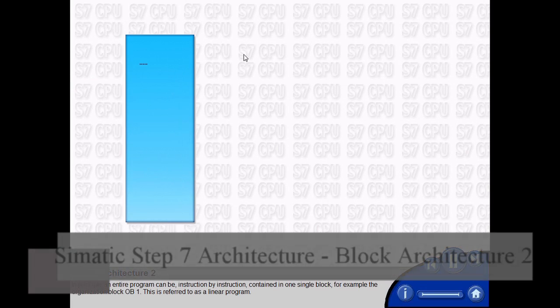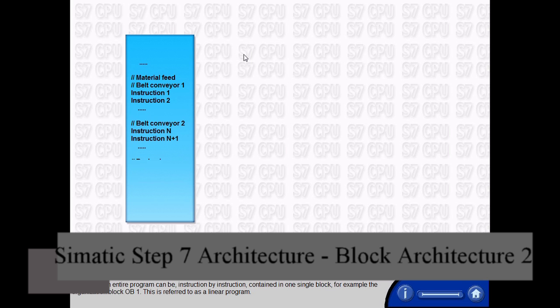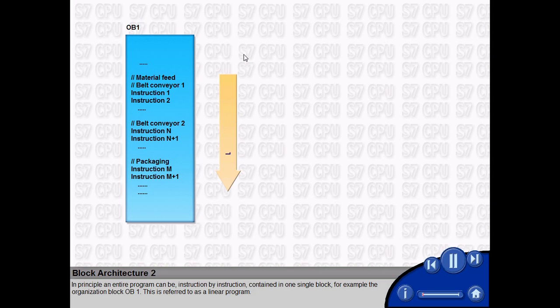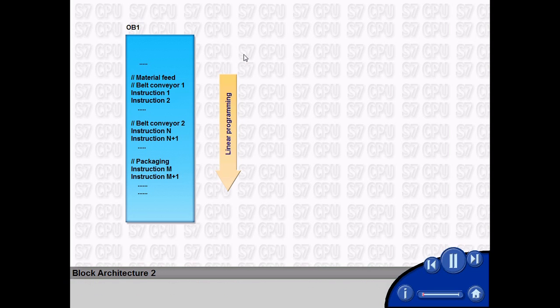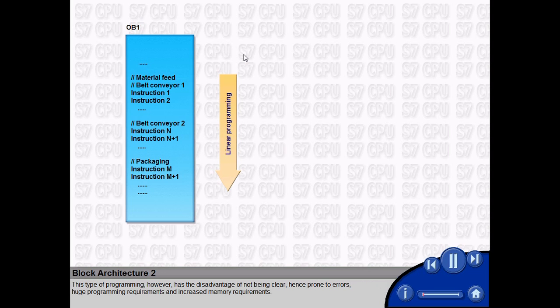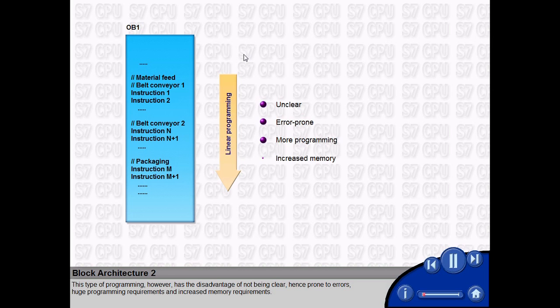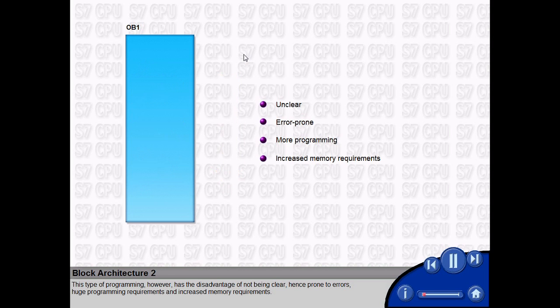In principle, an entire program can be instruction by instruction contained in one single block, for example the organization block OB1. This is referred to as a linear program. This type of programming, however, has the disadvantage of not being clear, hence prone to errors, huge programming requirements, and increased memory requirements.